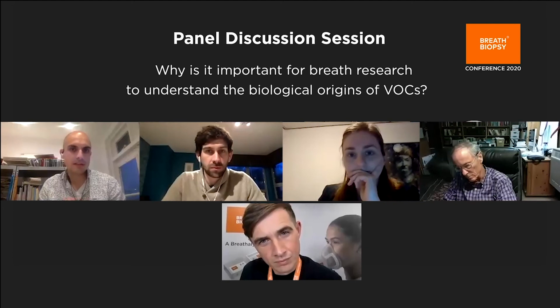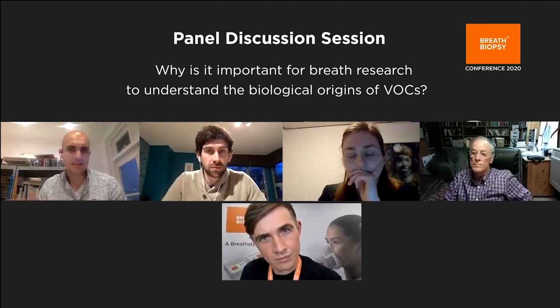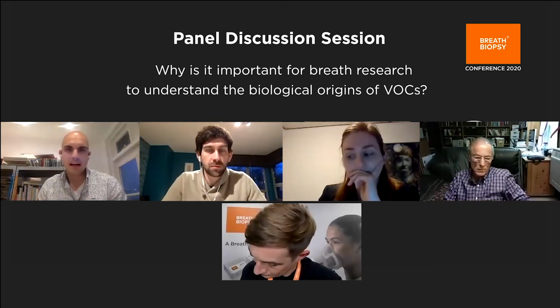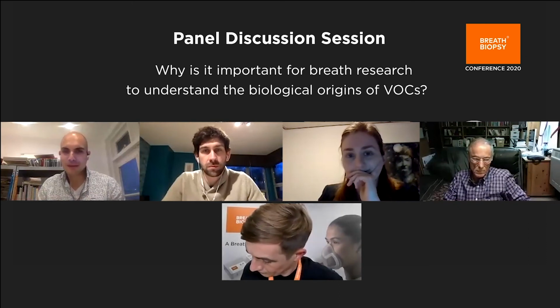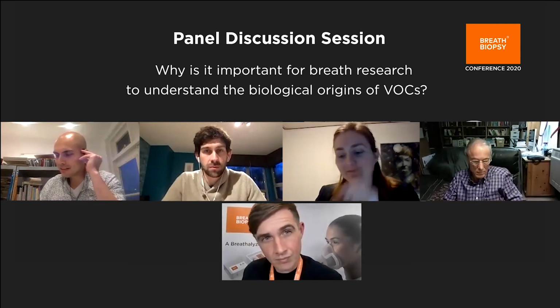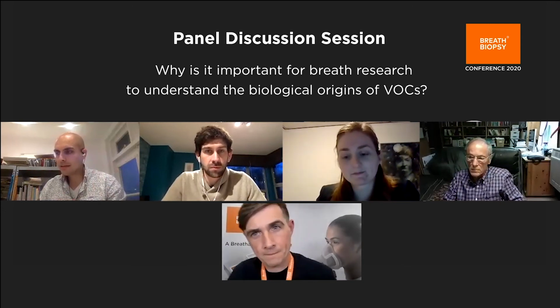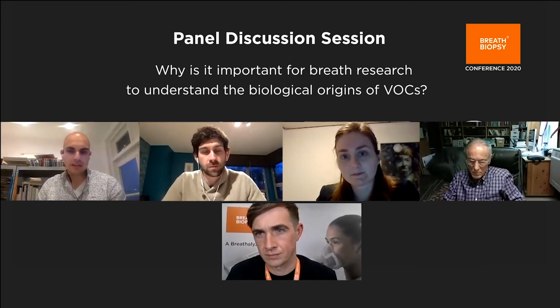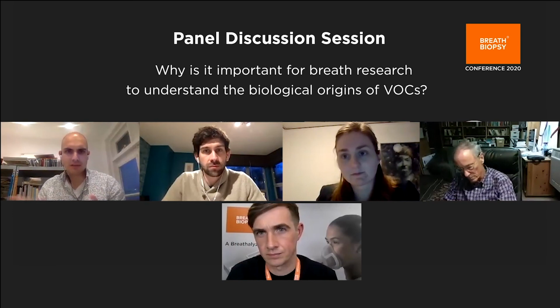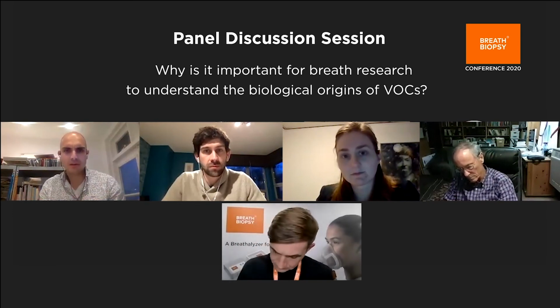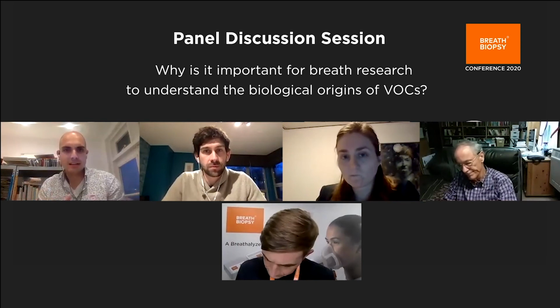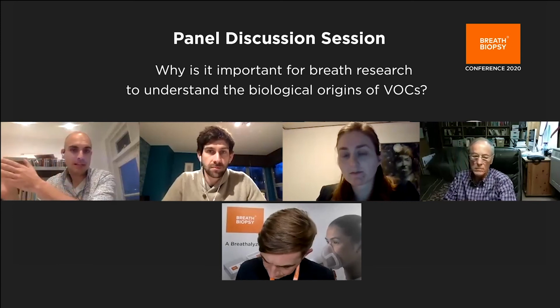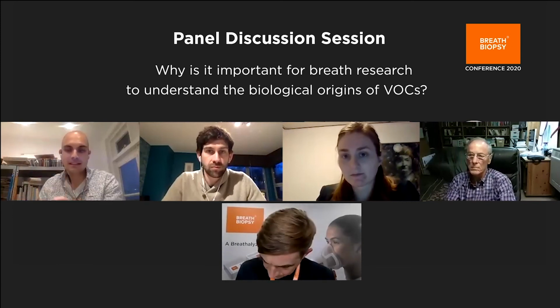First, understand what you're trying to detect, and then make sure that whatever sensor you pick is the most sensitive one to do so. I come from that background originally, and during my PhD did mostly e-nose work. One thing I really took from that learning was that, because you don't know what you're measuring, I started seeing drift over time. Is that relevant to my classification or not? And how do I calibrate my device? Because I can never calibrate it. If you knew what the compounds are, you could pick the best sensor and calibrate it with a mixture each time, because you know it needs to detect X, Y, and Z.